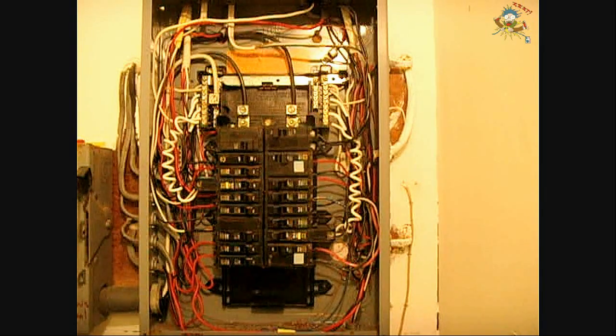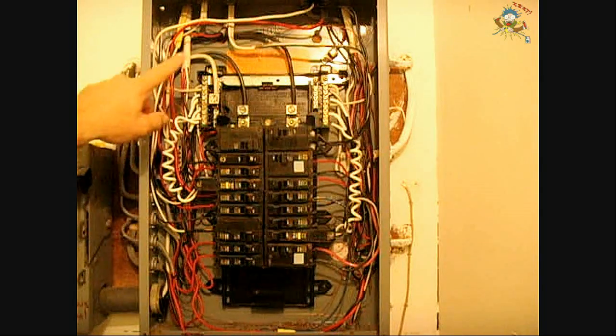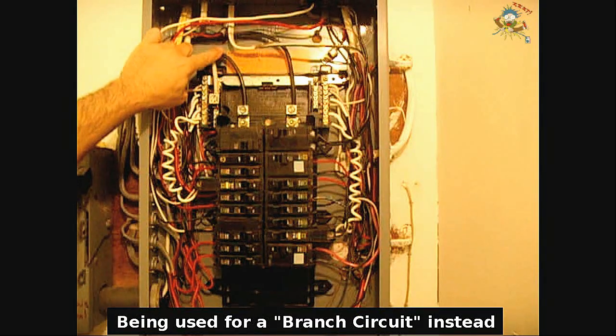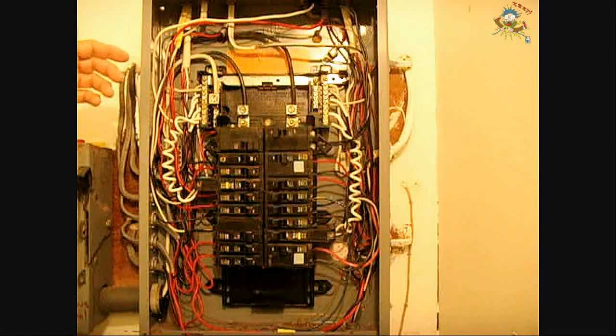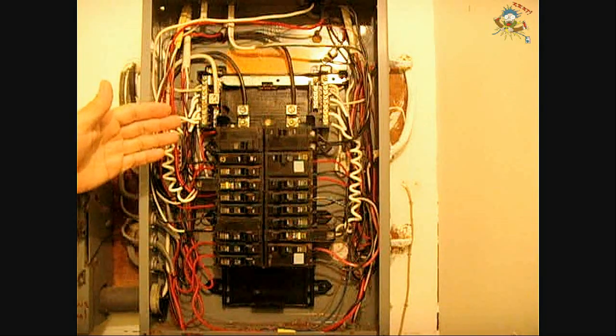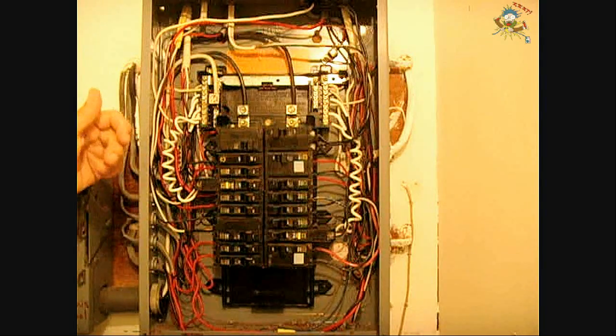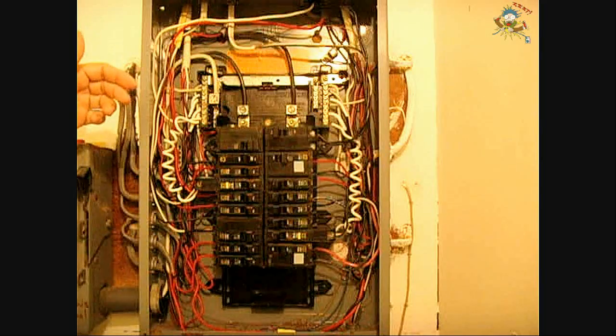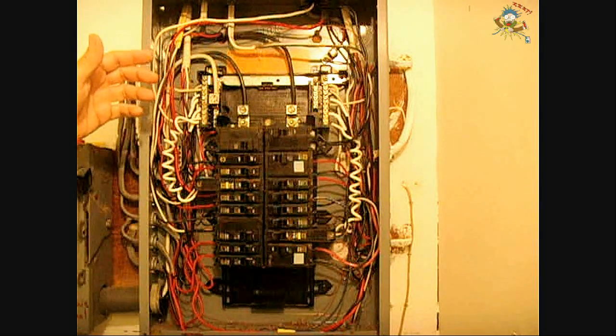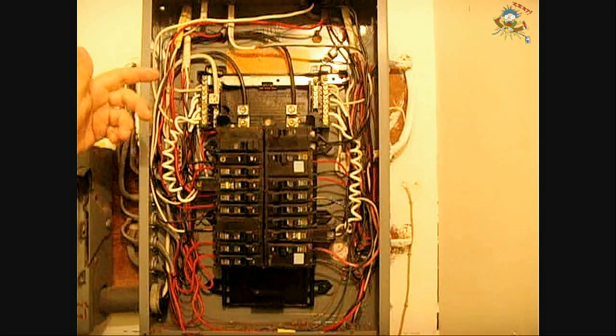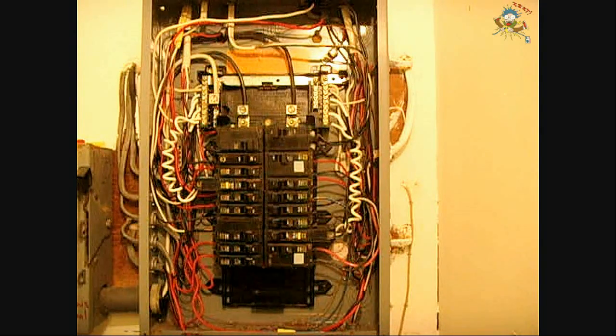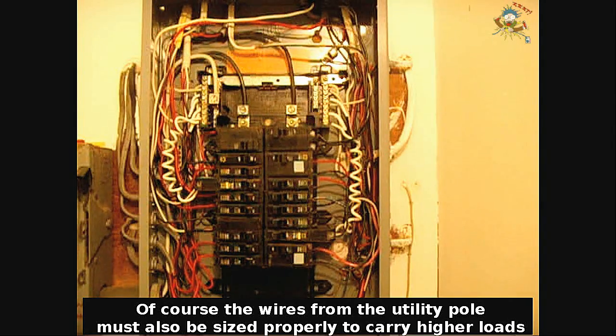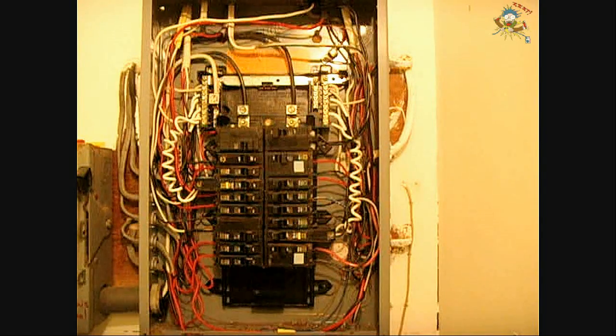If you do have a 70 amp breaker and it's feeding a sub-panel, because it's not being used as a service entrance conductor like you see here, this 4 gauge wire, because it's a service entrance conductor going into the panel from the utility, you're allowed to use a 4 gauge wire for 100. If you wanted to go to 110 amps, you would use a 3 gauge copper wire. If you wanted 125 amps, you would use a 2 gauge wire going into there. If you wanted 150 amps, you would use a 1 gauge wire. If you want 175 amps, you would use a 1/0 wire, or if you wanted to use a 200 amp service, you would have a 2/0 wire. Then it goes 225 amp, you would use a 3/0, and you'd have a 4/0 wire for a 250 amp service. And as I said earlier, you would use the next size thicker or the next size heavier wire in aluminum if you were going to do so.